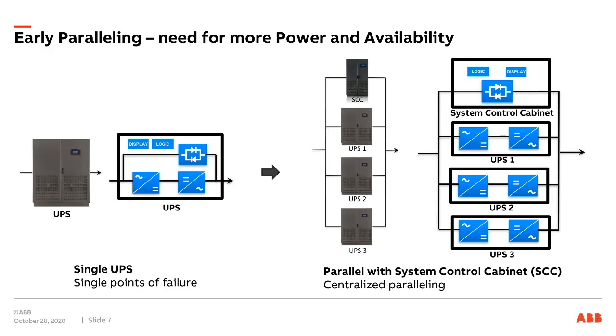The system control cabinet also holds the static bypass switch, which in this case has to be rated for the total system power. So this works now, and I should say, I think most of my drawings, this is my level of PowerPoint, so forgive me for that. I use 3 UPSs in parallel. Most manufacturers can parallel easily up to 6 UPSs, but to have it somewhat visible on the slide, I limited it to 3. So this of course serves the purpose. 3 inverters, 3 UPSs in parallel, can now support 3 times the power. Or if the load can be supported by 2 of the inverters, it offers what we refer to as N+1 redundancy.